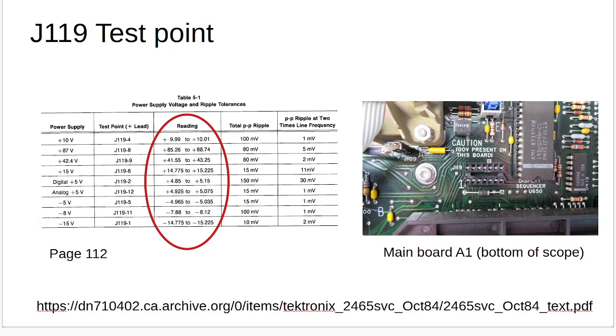On page 112 of that same service manual, table 5-1, you can see the various voltages that can be accessed there. The readings column shows you the range of values where that's possible to enter into the settings for a Datalogger. So each channel is differential, so you can put in a lower and a higher voltage range, and so each of the channels will be recorded similar to just an oscilloscope, except these can go on for many minutes or hours if you need.